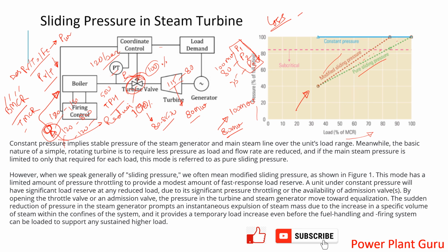But to have some margin for load change up and down, an inbuilt calculation is done. Based on that, it is having a little more margin, some more flexibility. It is always on a little higher side. You see from this point, let's say for 60% load, the pure sliding pressure is something less than the modified sliding pressure. So this much margin you will have to increase your immediate load.